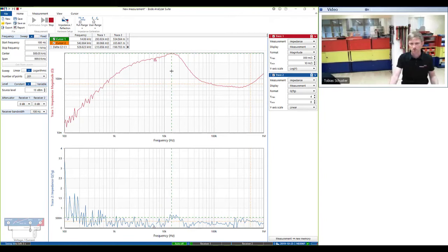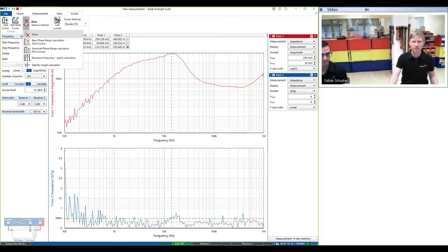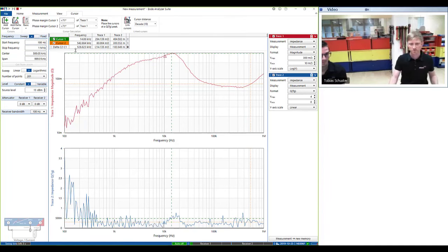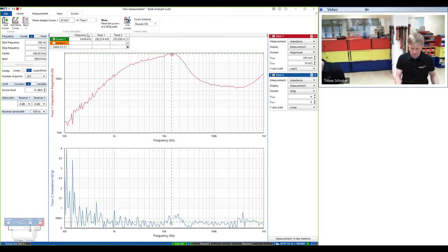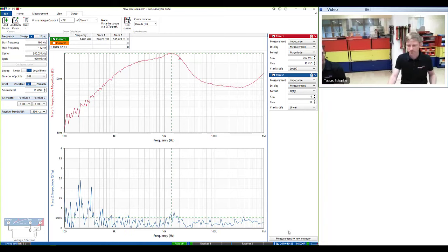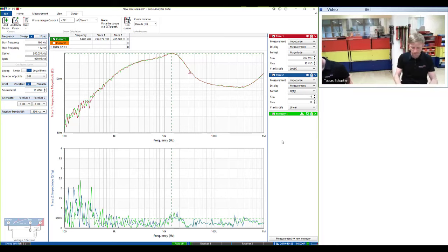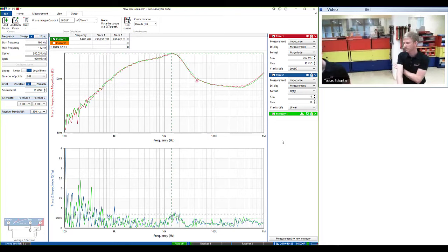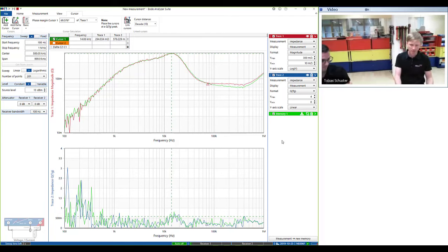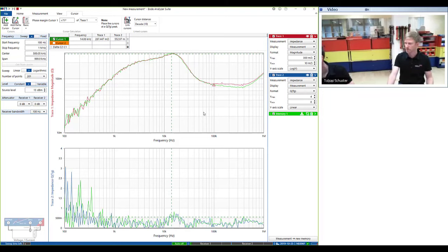I'm going to switch on the stability margin calculation, the phase margin calculation, and it says at cursor 1 something like 70 degrees. So everything looks pretty nice in that case. I'm going to store that to the memory. And now we'll try to change the operating point to find a really bad phase margin case, where we should have peaking in the Q. If I remember correctly from the previous webinar, when we went to 1 amp load current and minimum input voltage, there was a really bad phase margin left.